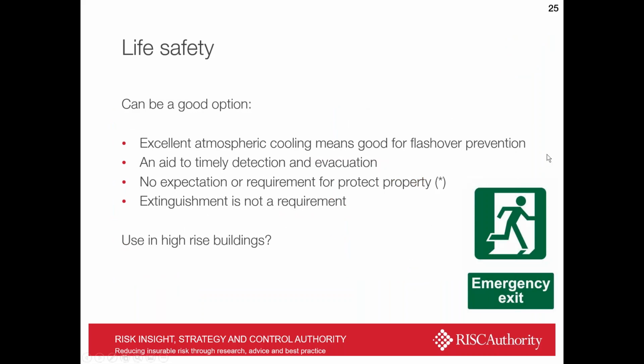But that said, for life safety purposes, we've seen some very good implementations. We know that they have the facet of exhibiting excellent atmospheric cooling, very good for flashover prevention, and really preventing fire growth in small domestic residences. An aid to timely detection and evacuation, and generally these are specified without an expectation or requirement for property protection, and as extinguishment is not required. It's more about getting people out of the building, and they can do that very effectively indeed. And obviously post-Grenfell, they've been proposed as a good measure for assisting the escape of occupants who can be quite remote high up in high-rise buildings, and we've seen some good examples on where that certainly is a feature.